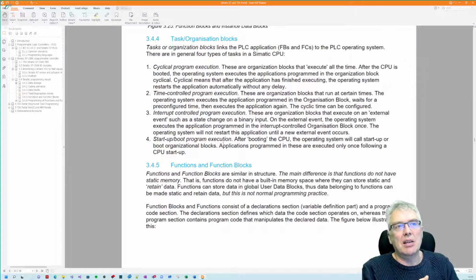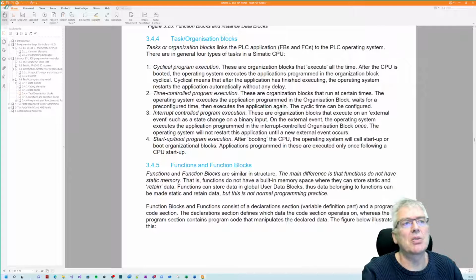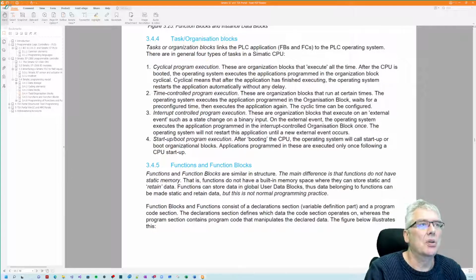So let's say the last time you controlled the process, a motor was running, and then your CPU stops, and then someone stops the motor, or maybe the motor stops because you are not controlling it anymore, but you remember, okay, it was running, and then you restart the CPU and it just starts the motor. Not good, especially not after 14 days, if your process has been stopped for 14 days. So important.